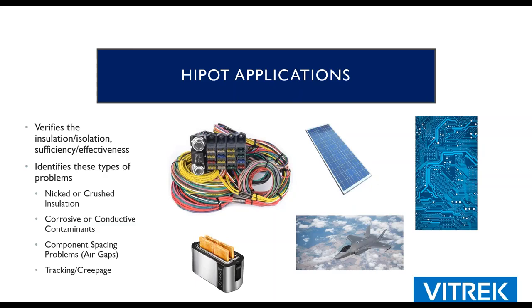If there is more, that could be because you have compromised insulation. Things could be corroded, contaminated, or it could just be designed wrong. Maybe you designed something and they built it in inches instead of millimeters, and all of a sudden you get it back and it's just straight wrong. That happens too. You want to verify that there's also the proper surface creepage, which is like linear distance. Sometimes instead of traveling through the insulation, it's easier for the electricity to go around the corner and travel on the surface. There could be some dirt or some moisture there that helps it creep along. And that's something that you're also going to be able to catch during one of these tests.